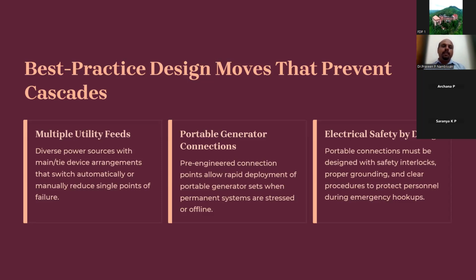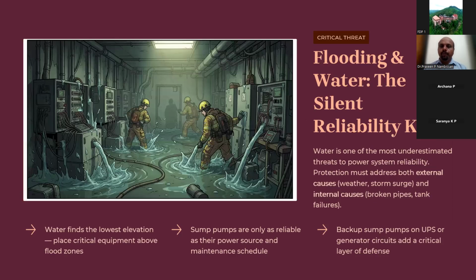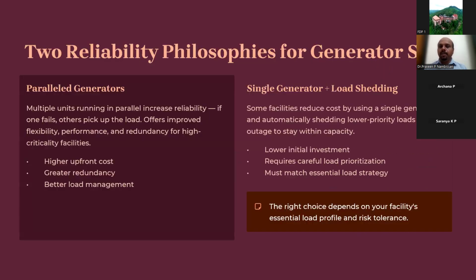Best practice design includes multiple utility feeds, diverse power sources with main or standby arrangements that switch automatically, plus portable generator connections and electrical safety by design. Flooding is a silent reliability killer because water always finds the lowest elevation, so critical equipment should be placed above flood zones.